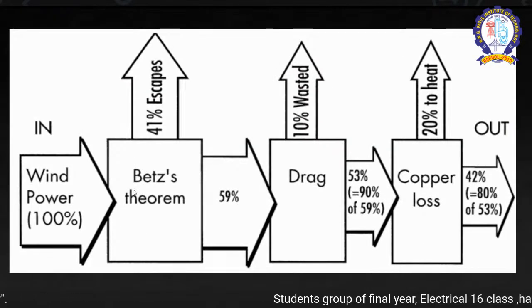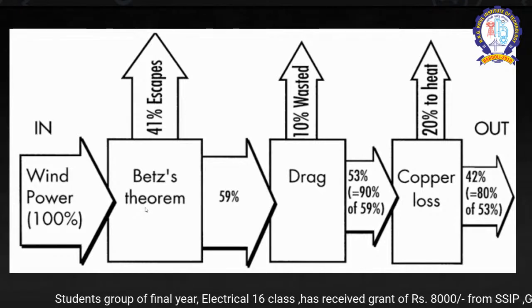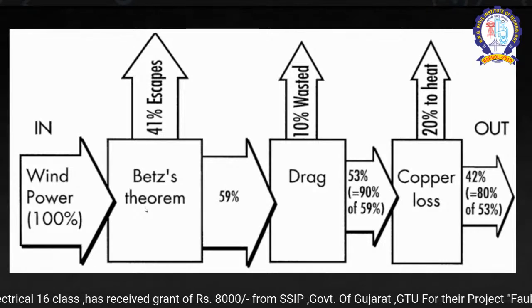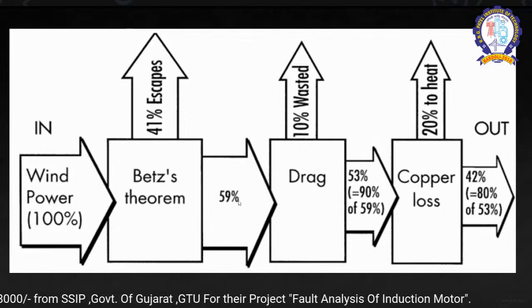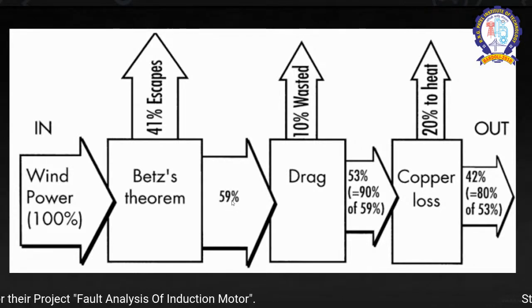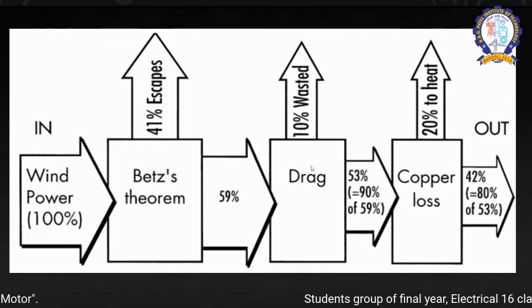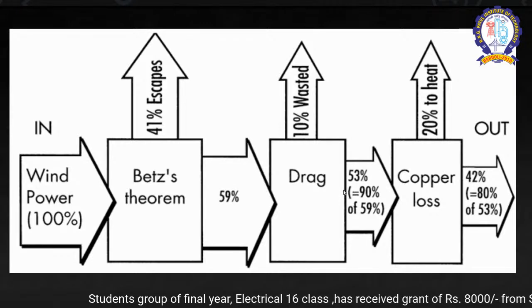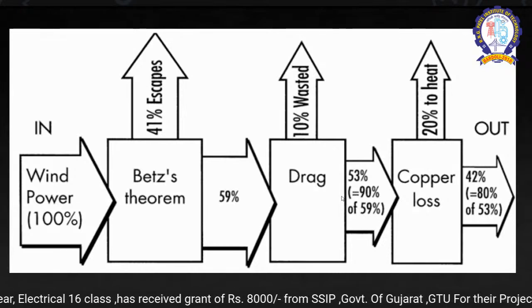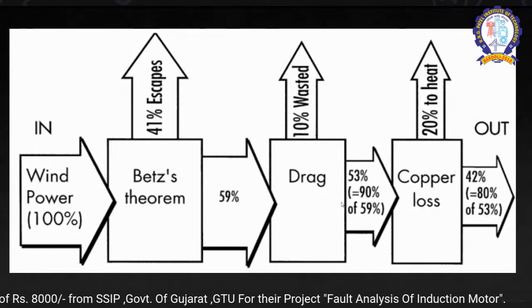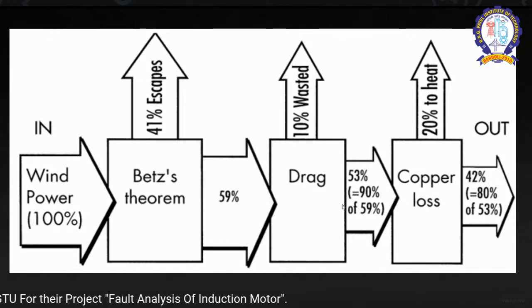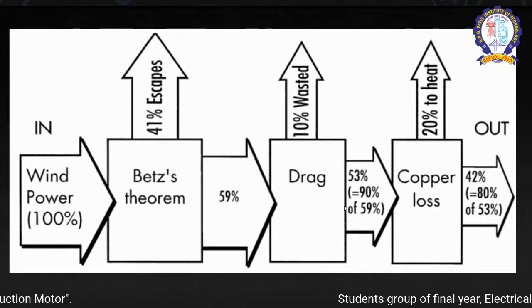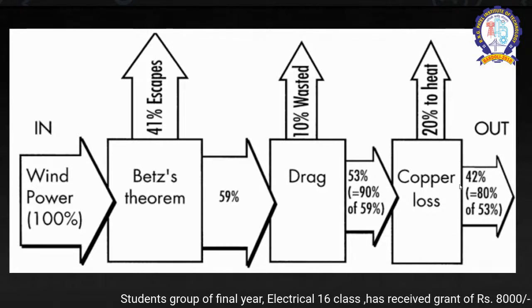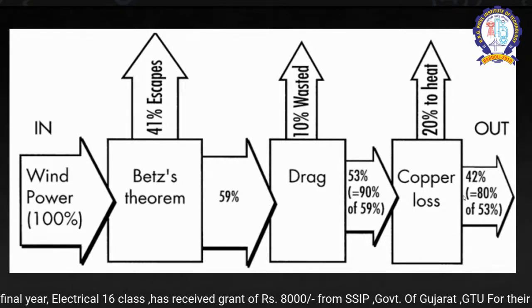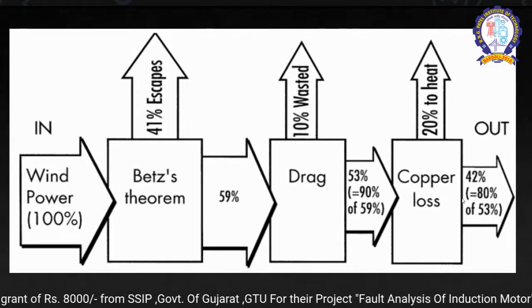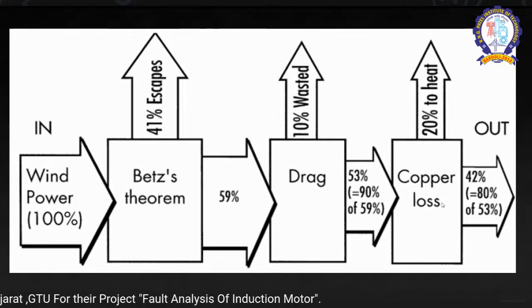Now, this theorem is known as the Betz theorem, where from the incoming wind power, 41% energy has escaped with the Betz theory. So the remaining 59% theoretically, usually the wind turbine observes the drag force. In drag force, 10% energy has been wasted. The rest, 53%, that is 90% of 59%, will still enter the generator, because we need to follow the energy chain. Then we have the copper loss of the generator, and 20% has already been absorbed in terms of heat losses. So we are getting only 42% of the energy. But this 59% again is not achievable. We can have 0.4 to 0.5 Cp for a large-scale grid-connected wind turbine.